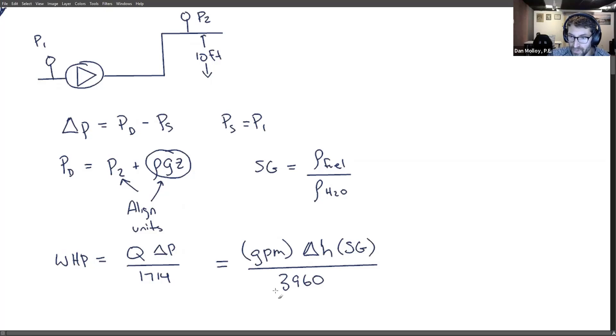And by the way, what's the difference between 3960 and 1714 for those who are paying close attention? This is a factor of, well, actually it would be dividing by 2.31, which is our convenient little rule of thumb for going from PSI to feet when it comes to pressure. So that shouldn't be surprising after you've done enough of these problems.